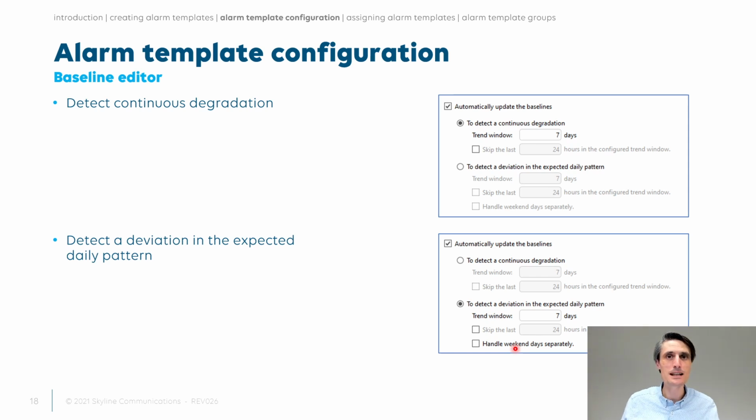Okay, so remember that normalization allows you to reuse an alarm template more broadly than a regular fixed alarm template, because if you're just going for the fixed thresholds, you might say something like, oh, let's duplicate it and have slightly different thresholds for this device. No, think about leveraging absolute or relative thresholds, so that you can reuse the same alarm template across different elements with a slightly different normal value.